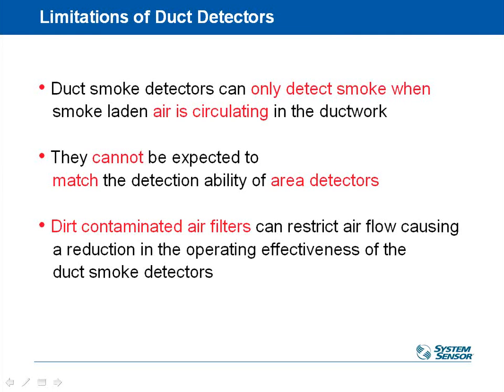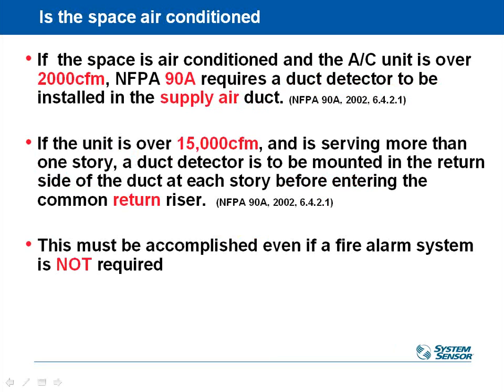And in a commercial building, we always have the fan and the air handler running during occupied hours for code reasons anyway. So it works good for that case. But it does not take the place of the smoke detectors in the actual space itself. Obviously, the dirtier the air system, the more ineffective a duct smoke detector can be. So it's very good advice, as well for other reasons, to keep your filter system clean.